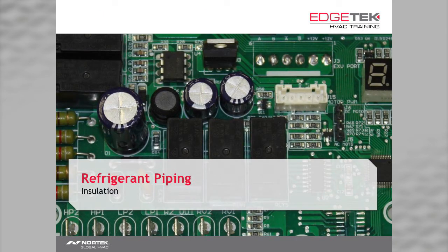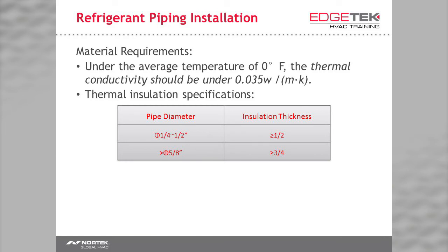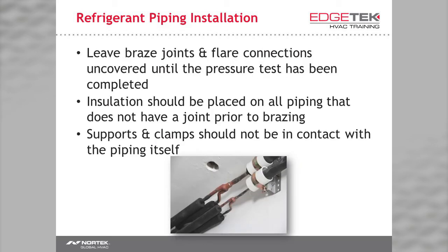Let's talk about the easy stuff now. Piping insulation. We do have guidelines for thickness and thermal conductivity, but the important thing is to check with the insulation manufacturer to determine the proper thickness for your environment. Chances are the type you have been using will suffice. However, all piping must be insulated. That's liquid and gas, all of it. Got it? Good. Y branches have insulating pieces included.